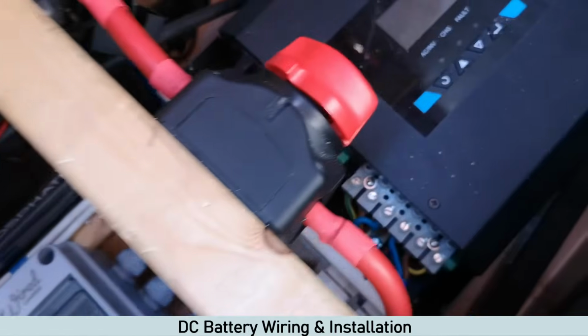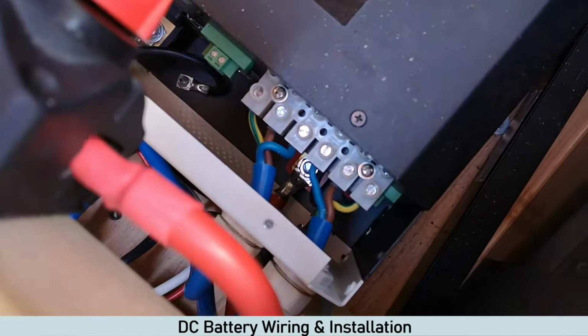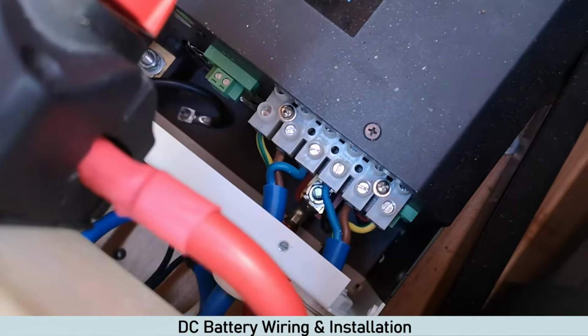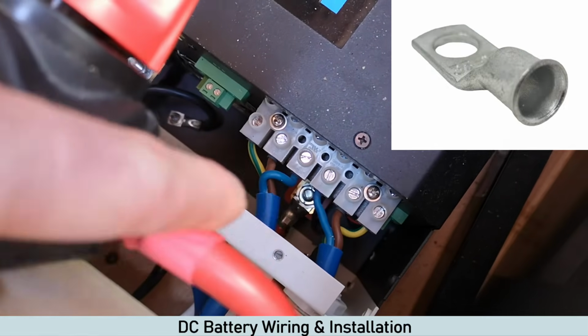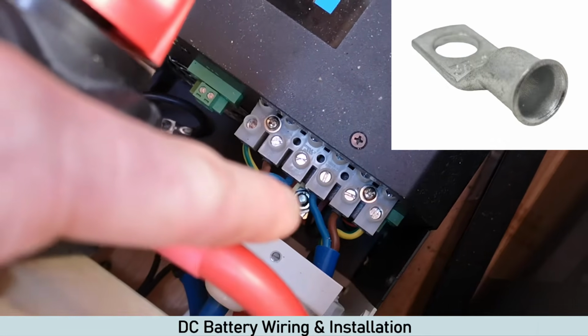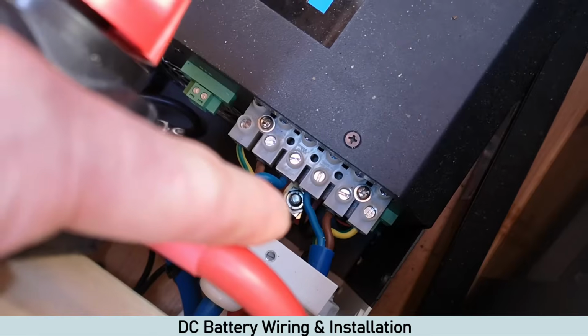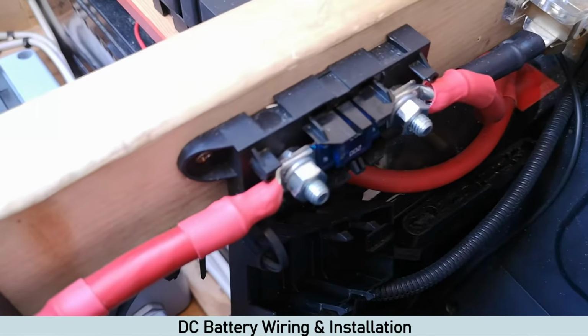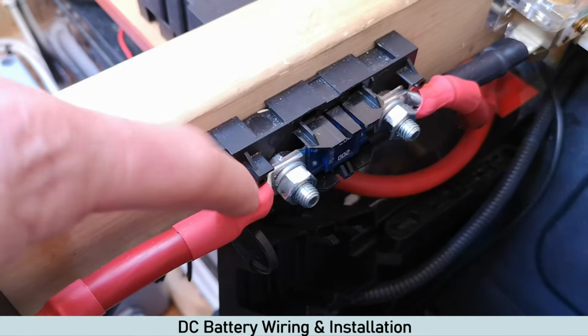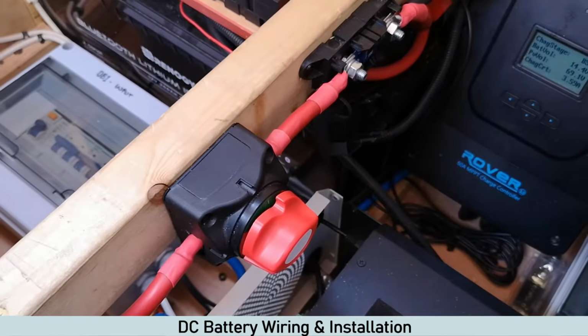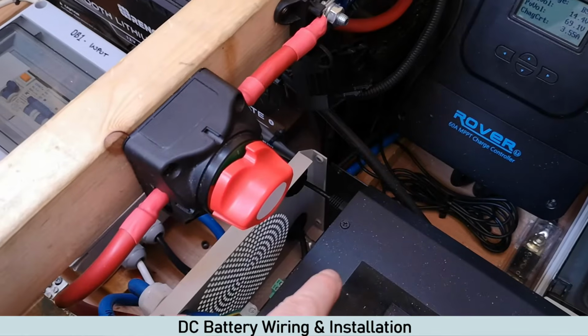The cable connections, we've used lugs, so I don't know if you can see it very well in there. I'll put a picture up actually to show you what a lug is if you're unsure. It's down there. The bolts are M8. So what a lug is, it allows you to connect a cable onto a bolt, which is what that is there. That's a lug. Now cable sizing, we have the 2000 watt inverter charger.